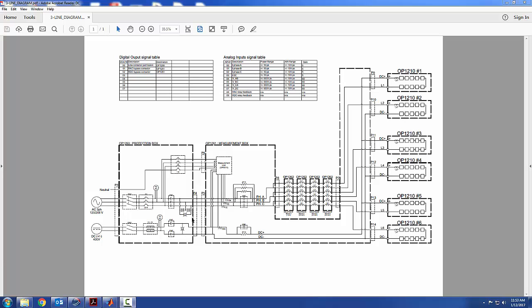The protection box is then connected to the measurement unit where you have the conditioning module that enables you to interface power signals to the simulators, and the pre-charge resistor on AC and DC with the bypass contactors required for normal operations.